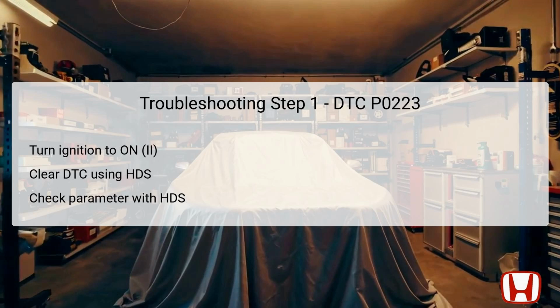The next crucial step is to check the parameters related to the TP sensor B using the HDS. You'll want to confirm that the voltage reading does not exceed 4.8 volts under normal operating conditions. If the current readings match this threshold, you've successfully duplicated the failure, allowing you to advance to the next steps in the troubleshooting process.